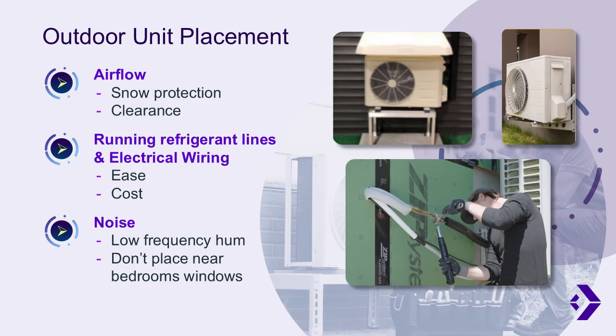Let's shift to talking a bit about outdoor unit placement design. A heat pump can be sized perfectly and installed beautifully indoors, but if the outdoor location is not right, you're going to feel it, literally. There are three big factors to keep in mind during the design phase of placing outdoor units. First, airflow. These outdoor units need to breathe. Placing them too close to a solid wall can choke off airflow and hurt performance. Remember, clearances matter. Be intentional with placement. Look for areas away from shrubbery or debris-prone spots, like under a damaged gutter.